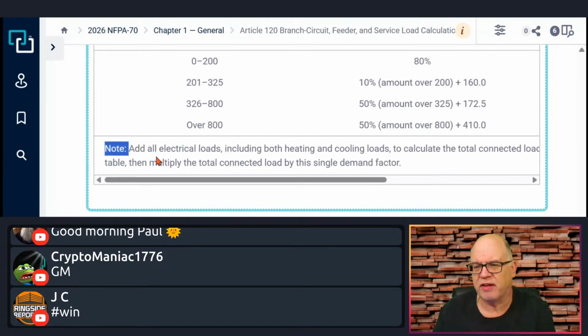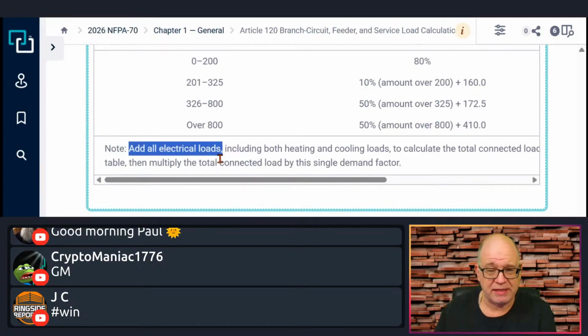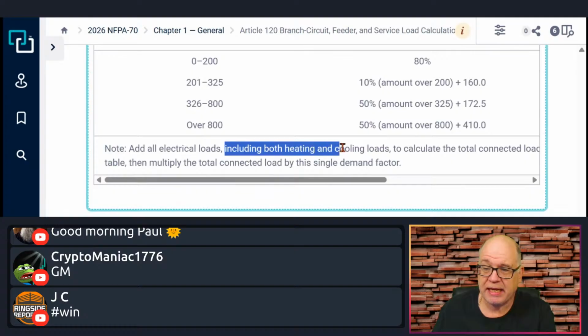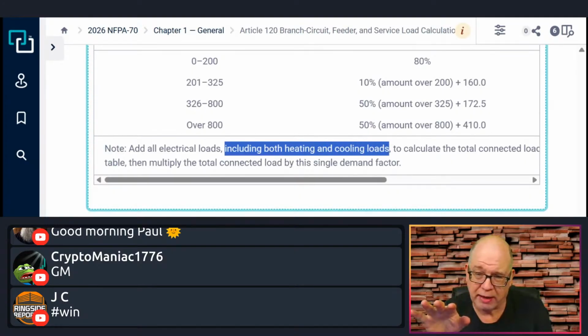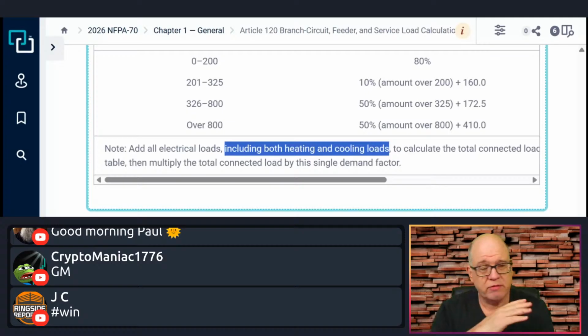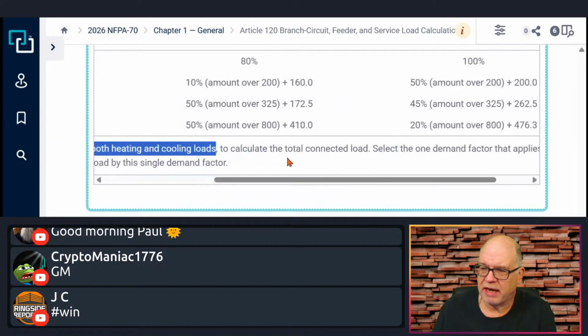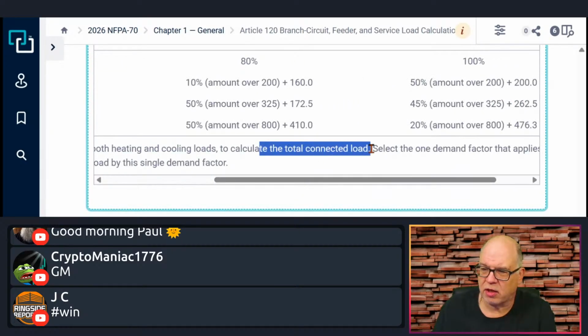And here's what it says: add all electric loads, add them all up. Couldn't be any easier than that, including both heating and cooling loads. So AC and heat, there is no issue here on the optional method of a non-coincident. Add all your loads up, okay? And then it says to calculate the total connected load, just everything, right?